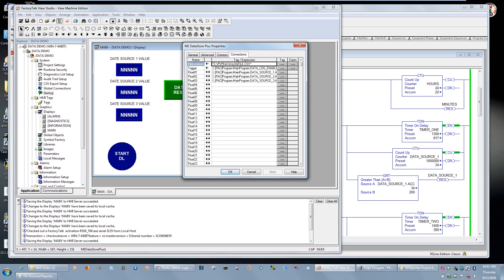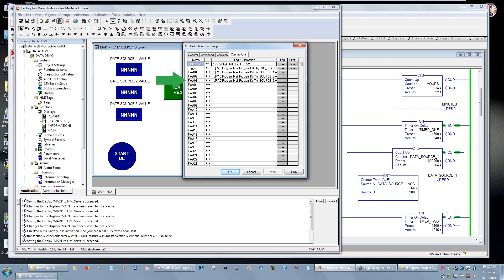The Connections tab is very important. The top section specifies where you want to put the CSV file and what to call it. In this example, because I'm writing to a C drive in VMware, it's C colon slash the folder name, then the file name — in my case, a PVP data folder and a log file dot CSV. You can use multiple nested folders just like any Windows path. Note there are quotations around it, which tells the ActiveX how to write and dynamically change the file. Below that is the trigger — a bit in the emulate that tells the ActiveX model when to start and stop. Then you have the actual value points, the three timer sources I showed earlier.